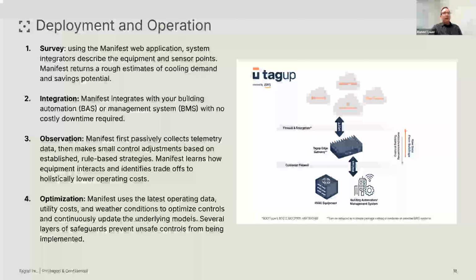If that's at all promising, we can quickly move to integration, which typically includes installation of a small gateway device, basically a small industrial computer set up at the site with access to the subnet of the BMS or BAS, giving us access to the sensor data already collected and to the control set point. The gateway then communicates that data back and forth to our cloud. In most cases so far we haven't installed new sensors at the site, because for basic condenser water set point optimization, nearly all the sensors are already there.